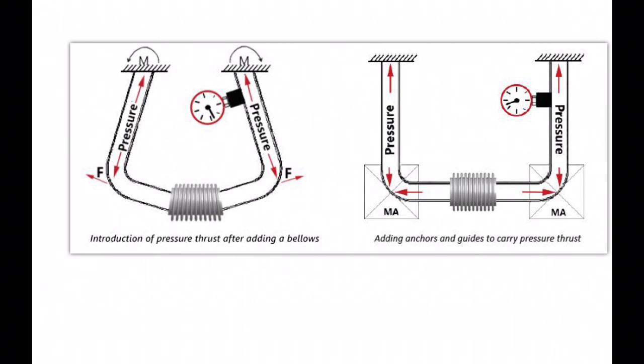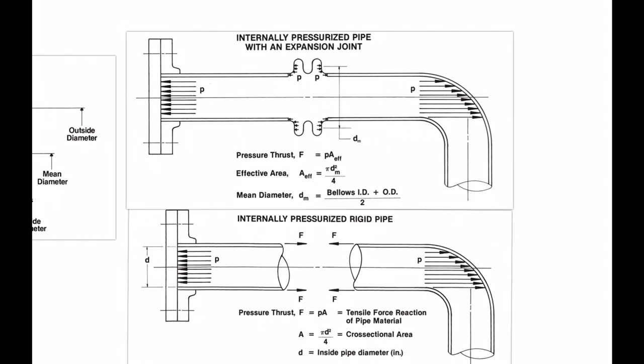In the second example as well, we are introducing a bellow as shown here. Earlier this particular F was simply pressure times the cross-sectional area, but now since we have introduced an expansion joint, the area is slightly modified. This dm corresponds to the mean diameter. So there is an extra load because of the bellow convolution. Let us look into that form in more detail.